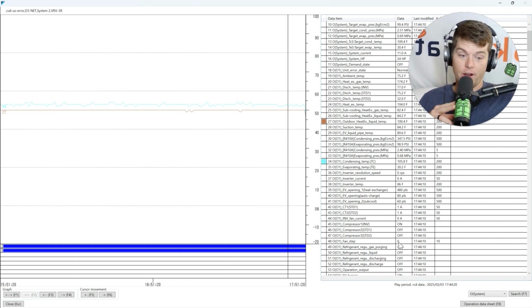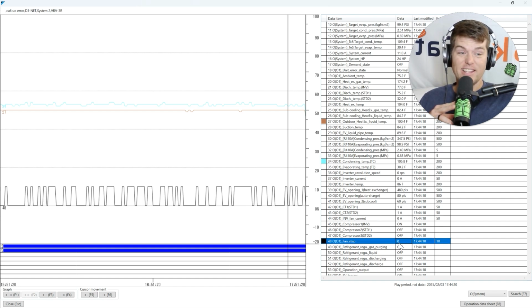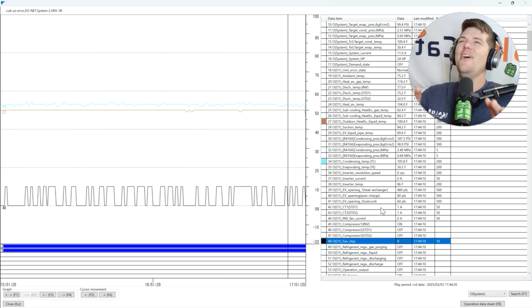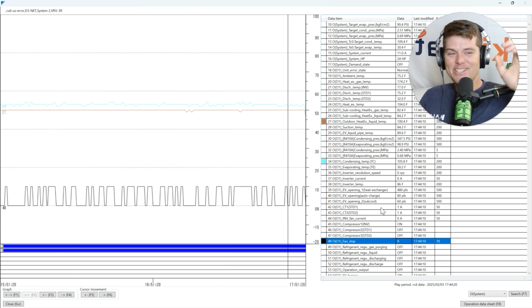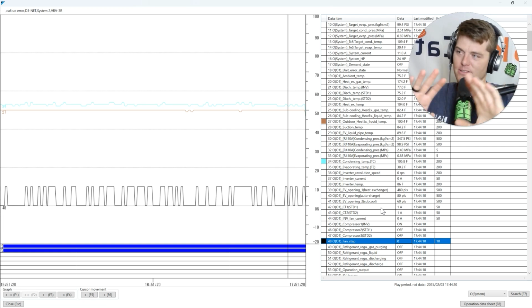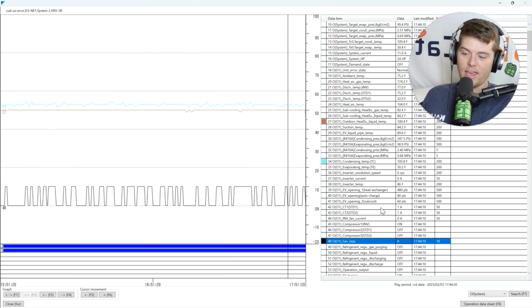What if we go down here and we look at the fan step? It's at 0. What does that mean? That means it's off. Wait, hold the phone. The submodule has got no gas. Okay, it's closed, shut down for construction purposes. We'll reopen in the spring. The master module is getting hot gas, but it's making 5 degrees of subcooling with 0 air flowing across the heat exchanger. It's magic, right? It's an ambient subcooler. That's what it is. It's new technology. Don't worry about it. It's too complicated.